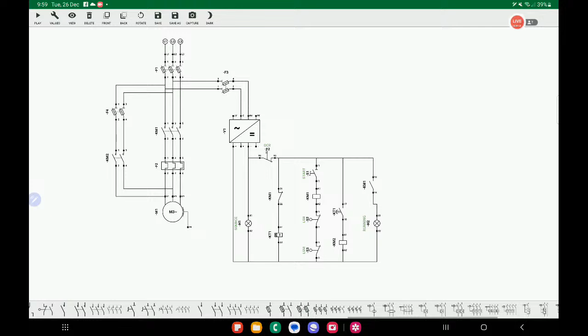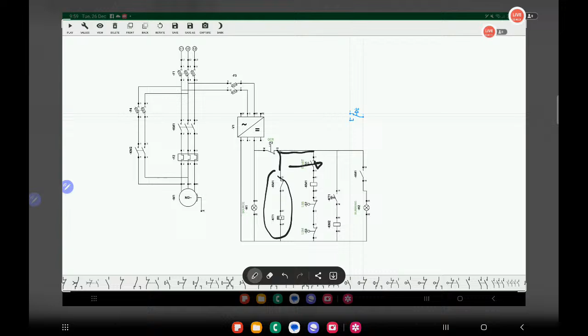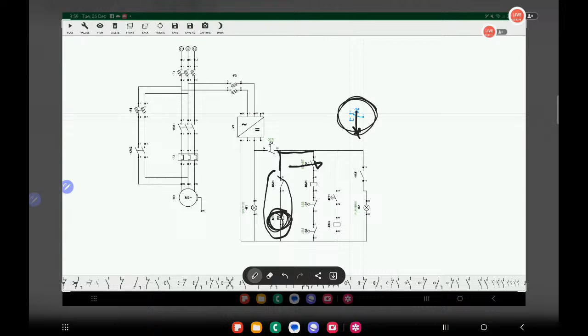Okay, let's say this one, this S4. If you can see, we need to separate the system. This is the space heater. Okay, we need to separate this space heater circuit onto this line so that whenever we start the system, this one will not keep on activating on, off, on, off. So it only means that we will use this S4 switch, so that once we switch off the unit, then that would be the supply voltage go to the KT1 timer. And then we will put another indication light that the space heater is running. So we will cut this line. We will cut also this line. This line, we will connect. Okay. So we will use this switch. All right. So this is in off position.